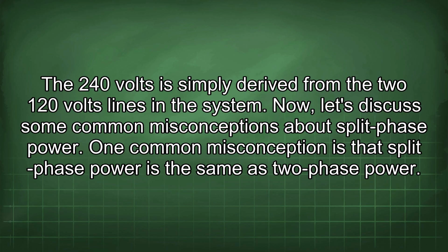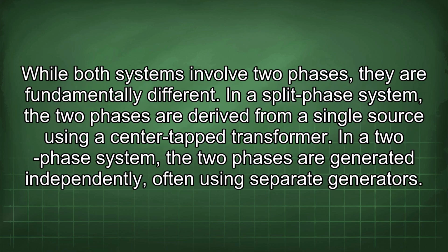Now let's discuss some common misconceptions about split-phase power. One common misconception is that split-phase power is the same as two-phase power. While both systems involve two phases, they are fundamentally different. In a split-phase system, the two phases are derived from a single source using a center-tap transformer. In a two-phase system, the two phases are generated independently, often using separate generators.